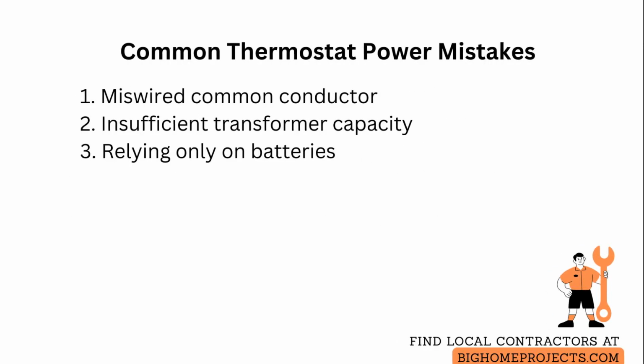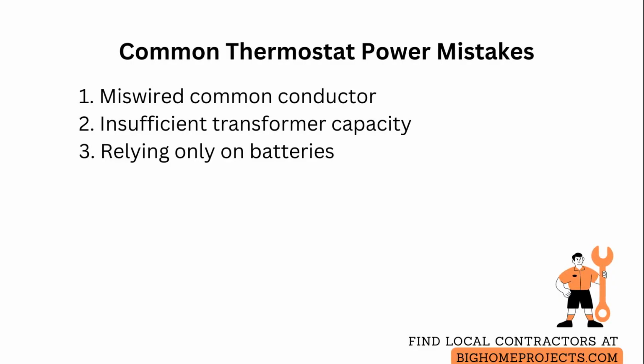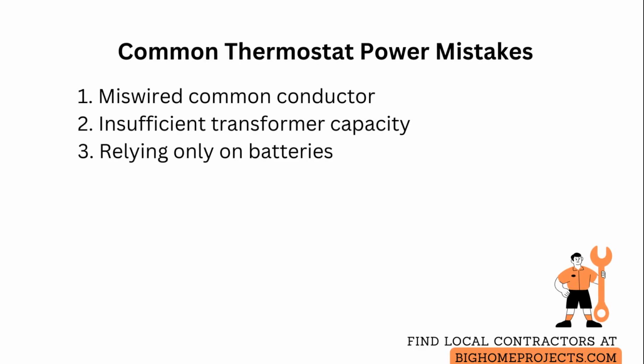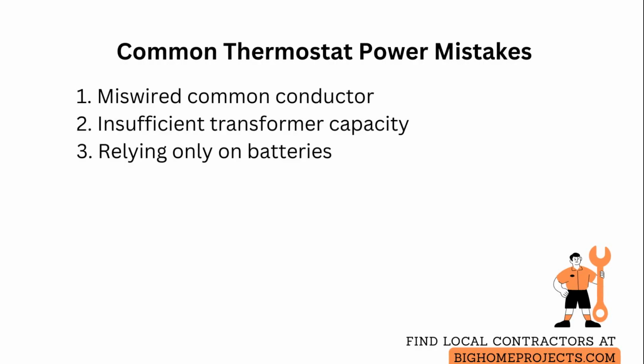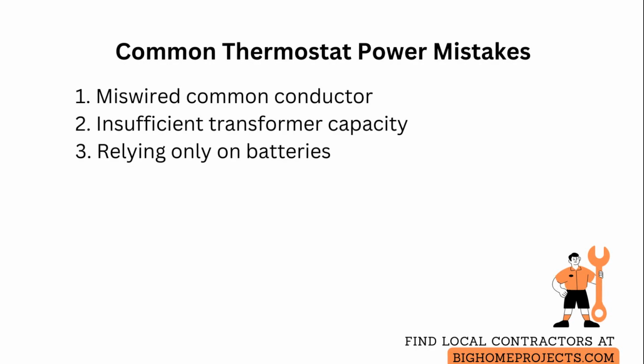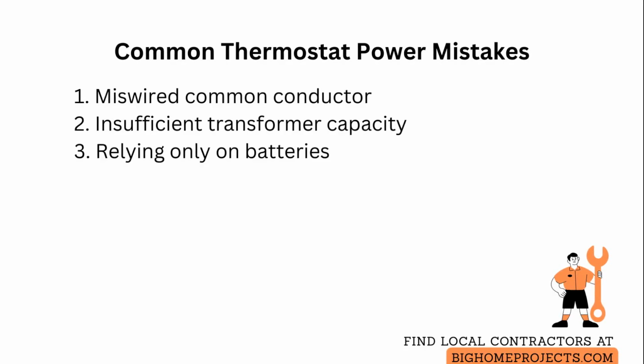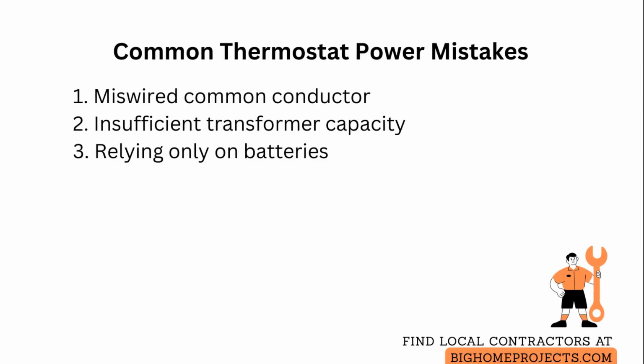Common issues include miswired common conductors that appear connected but are not tied to the correct transformer, which you can fix by tracing the common back to the air handler or control board and confirming continuity with a meter. Another frequent problem is insufficient transformer capacity, causing devices to reboot or batteries to drain, which you solve by calculating total load and upgrading to a higher rated transformer or relocating non-essential loads.